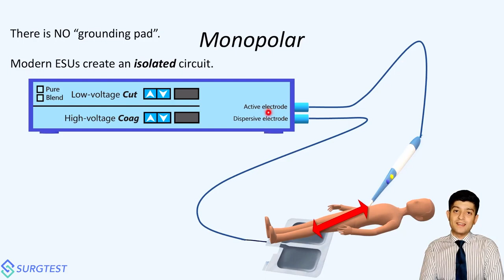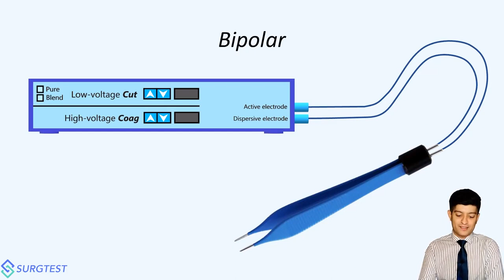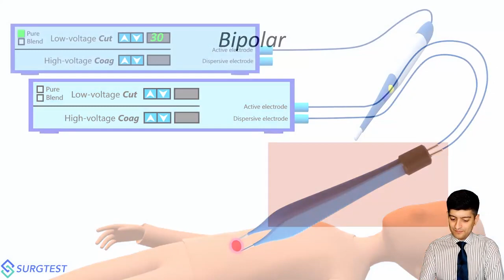The bipolar devices that we'll end up using have both of these wires essentially going into the same device. Now you may be arguing that, no doc, I've seen a single wire for bipolar devices. Yeah, it's a single wire, but within it contains 2 different wires, okay? Essentially both the active and the dispersive electrode bits go into the same energy device. And when you apply bipolar devices to patients, the electricity flows only through the small amount of tissue that is placed within the jaws of the bipolar device.